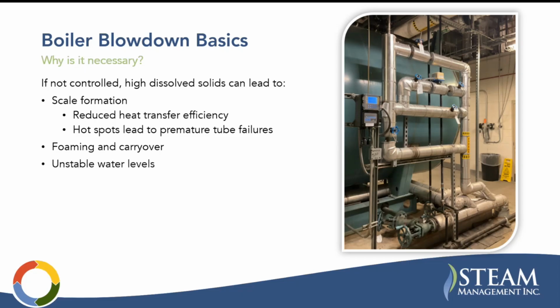What it's also going to do is cause foaming. As the dissolved solids build up in the boiler water and steam is generated, it will start building up a kind of foam or scum layer on top of the boiler water. If that foam gets significant enough, it'll start getting carried away with the steam. So then you're getting this dirty foam in your steam, giving you wet steam and dirty steam. Say you were cleaning medical equipment in an autoclave, you'll start noticing spots on the equipment, just getting poor results, but also getting wet steam and fouling in your steam system. So it leads to a lot of problems there.